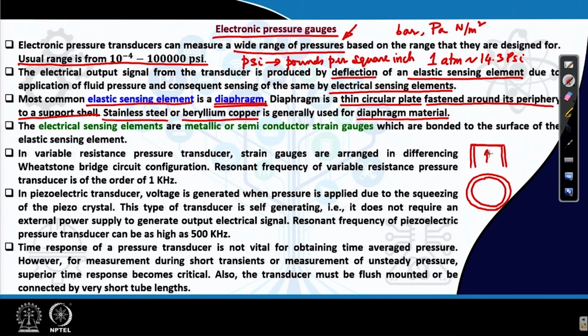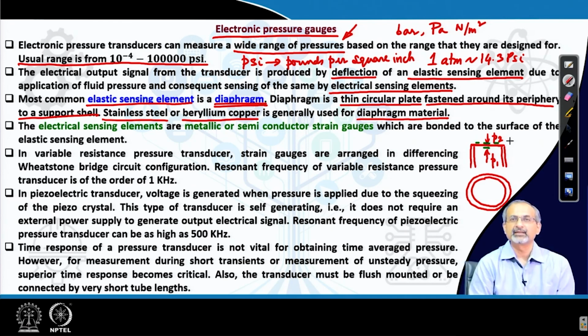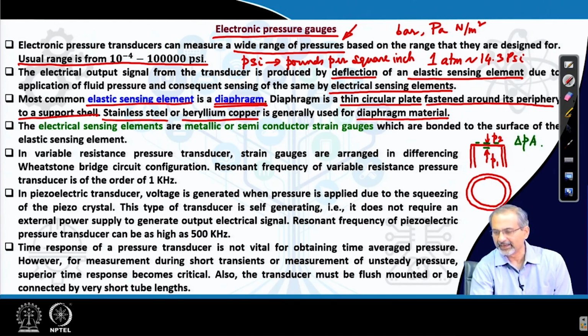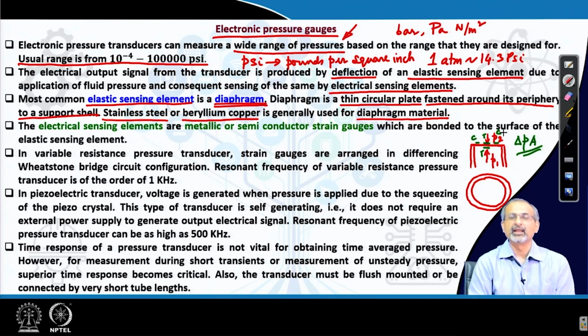So, let us say you have two different pressures from bottom and top. So, there is a differential pressure based on which this diaphragm will deform, and of course, you will have to have the electrical sensing elements, which means the strain gauges. If you bond them on or connect them on that diaphragm appropriately, so that a pair of them are in tension and another pair in compression, then obviously the strategy would be again to build a Wheatstone bridge out of those resistances, configure them in a differencing circuit sense, and make them respond to the force, which is basically coming out of this differential pressure into the area on which it is being applied. So, let us say if in this configuration the pressure causes tension here and a compression here, then that automatically will help you configure a Wheatstone bridge.